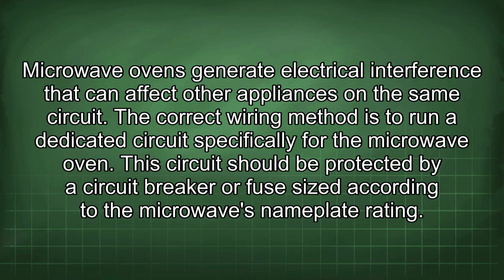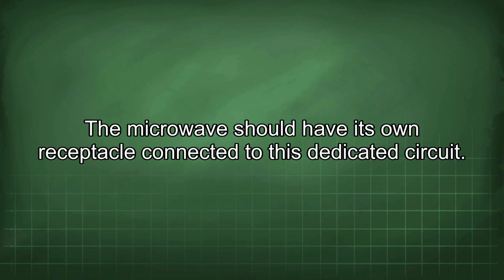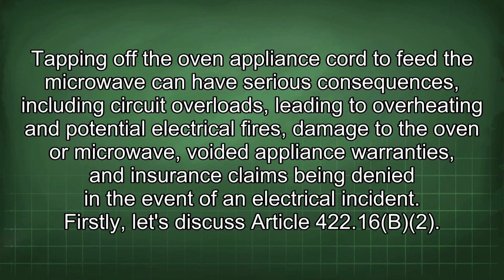The correct wiring method is to run a dedicated circuit specifically for the microwave oven. This circuit should be protected by a circuit breaker or fuse size according to the microwave's nameplate rating. The microwave should have its own receptacle connected to this dedicated circuit. Tapping off the oven appliance cord to feed the microwave can have serious consequences, including circuit overloads leading to overheating and potential electrical fires, damage to the oven or microwave, voided appliance warranties, and insurance claims being denied in the event of an electrical incident.